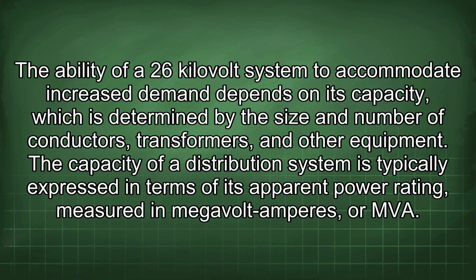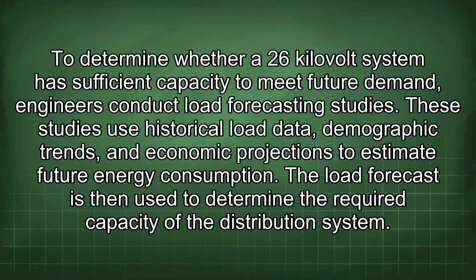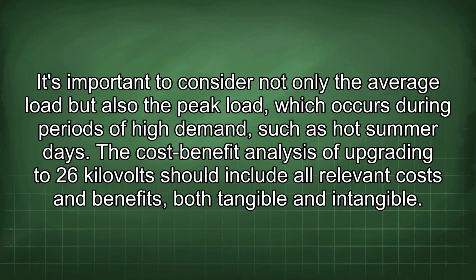or MVA. To determine whether a 26 kV system has sufficient capacity to meet future demand, engineers conduct load forecasting studies. These studies use historical load data, demographic trends, and economic projections to estimate future energy consumption. The load forecast is then used to determine the required capacity of the distribution system. It's important to consider not only the average load but also the peak load, which occurs during periods of high demand, such as hot summer days.